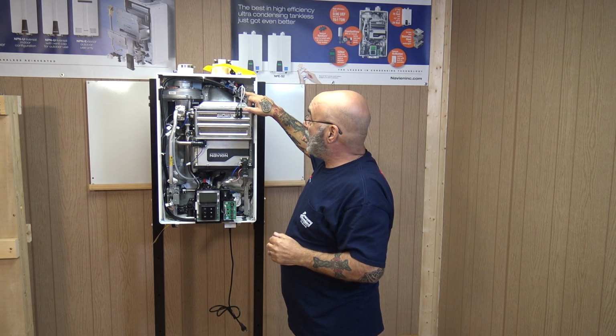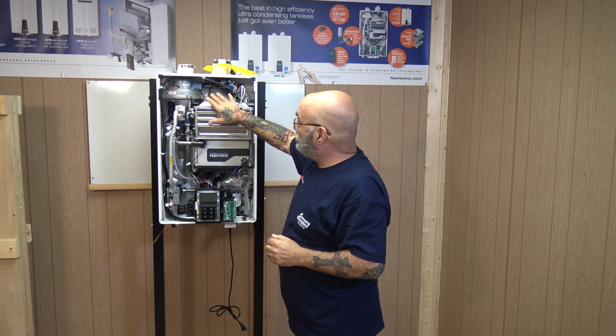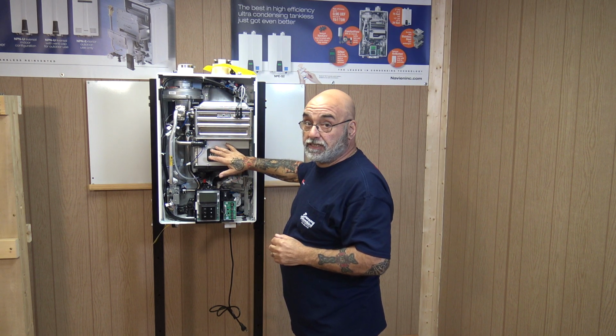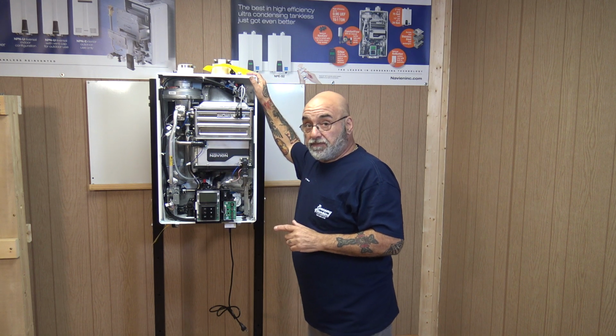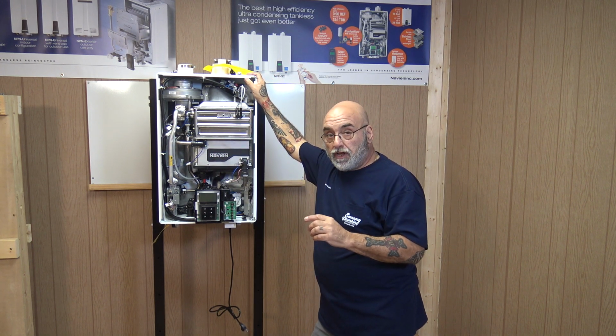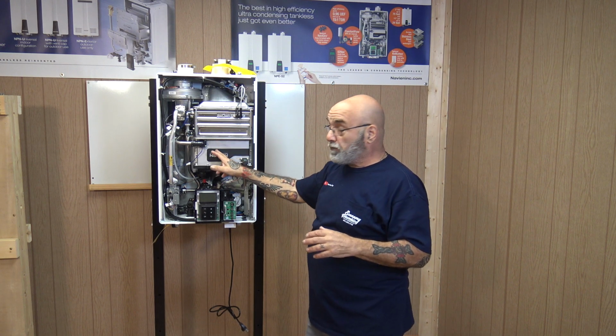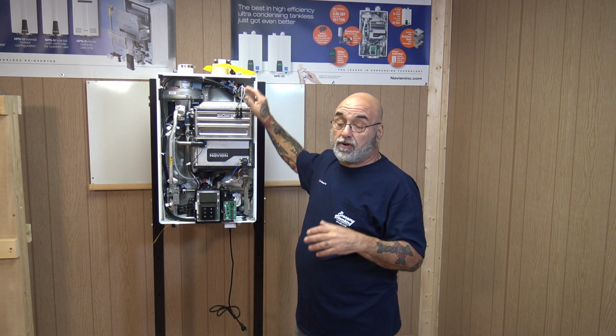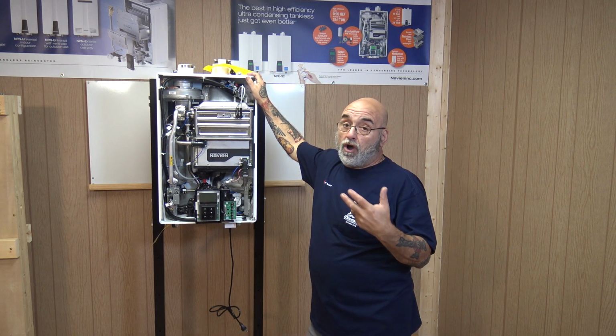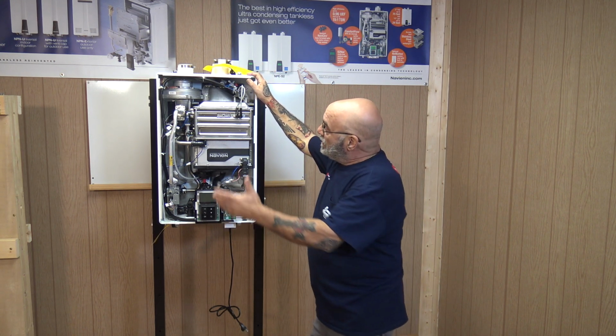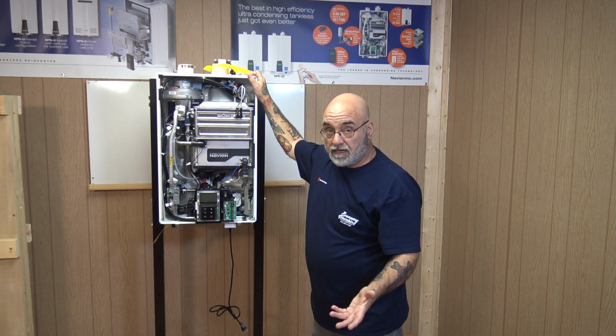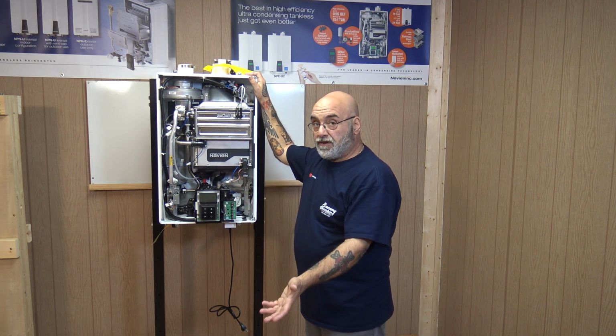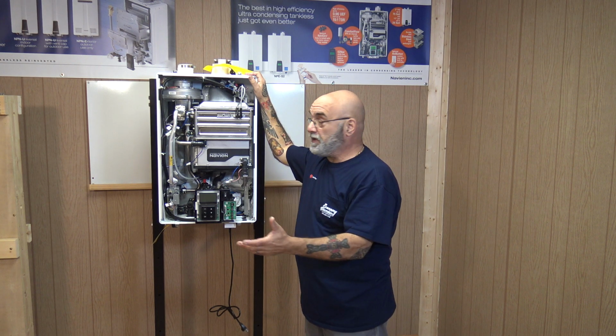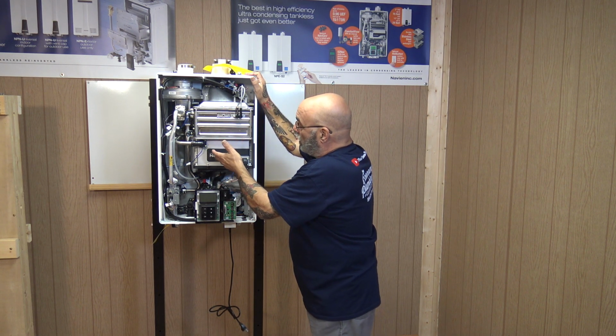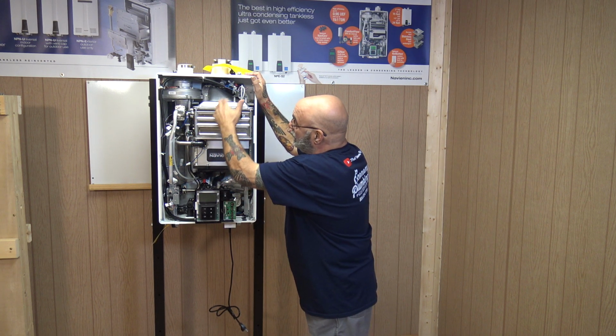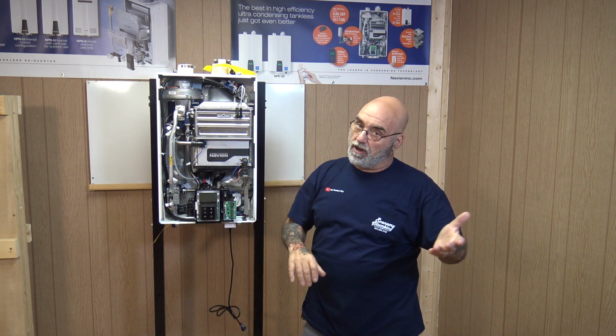You even get a new igniter. So you're getting the burner, the primary and secondary heat exchanger. So if your heat exchanger fails, you don't have to put 3 - either they're going to give you a primary or a secondary, then you got to put the burner, new gaskets, new screws, O-rings, yada yada yada. Here, you just take the heat exchanger out, take the brand new one, it's assembled in one piece, put it back into the unit, put your screws in, tighten it up, and reassemble everything. Again, we're going to go through that.